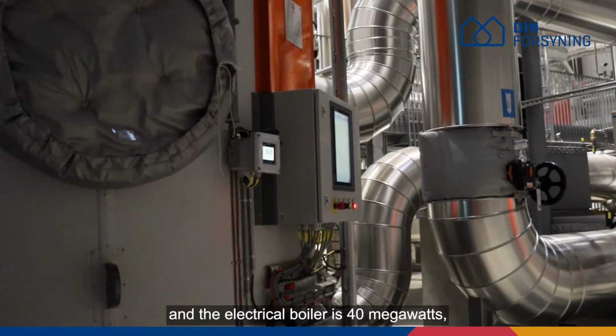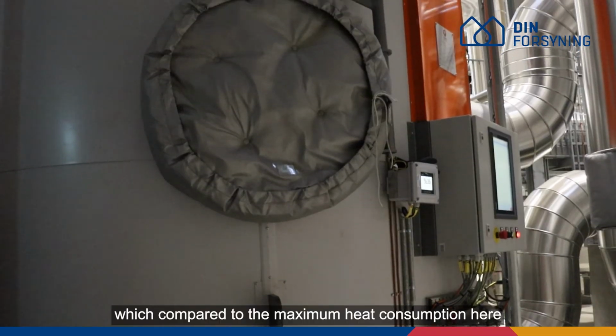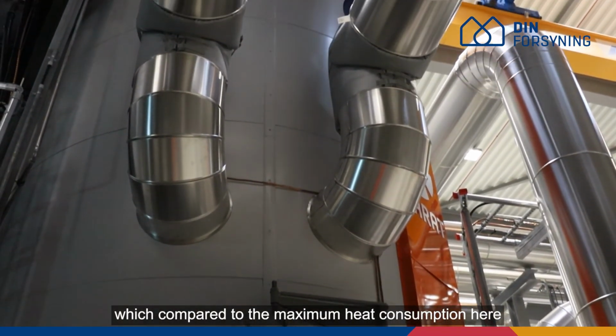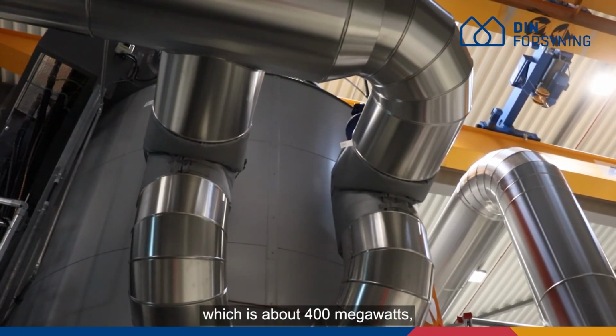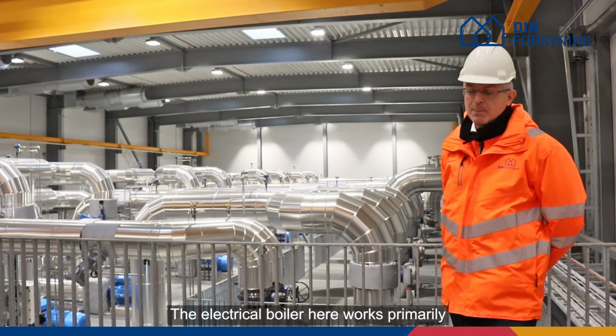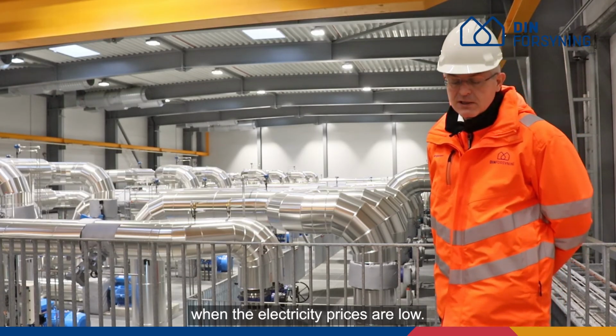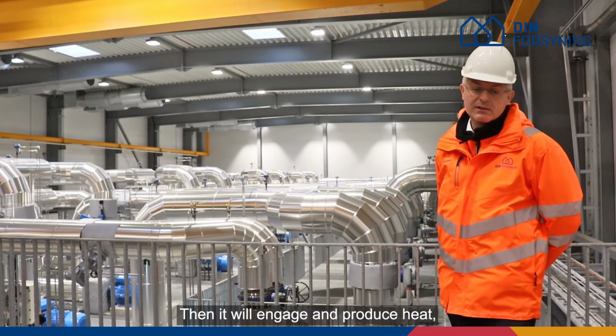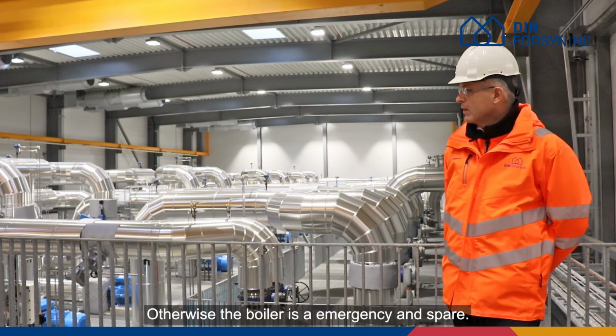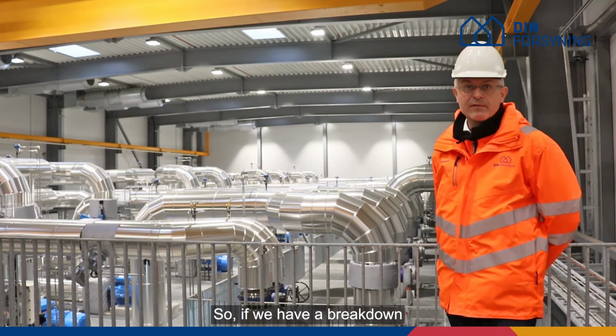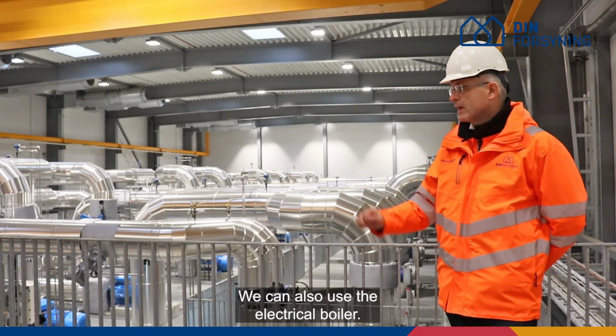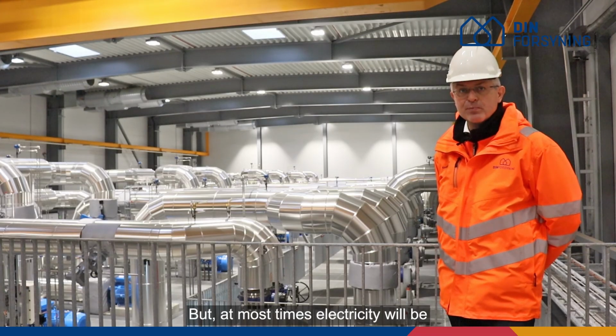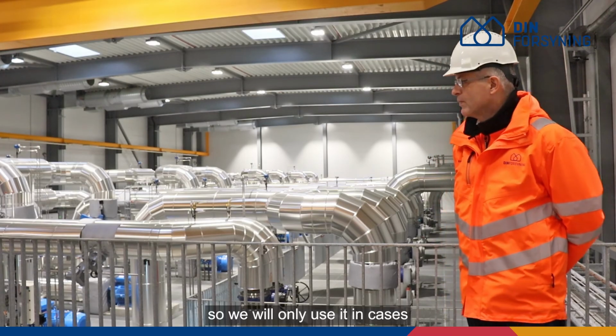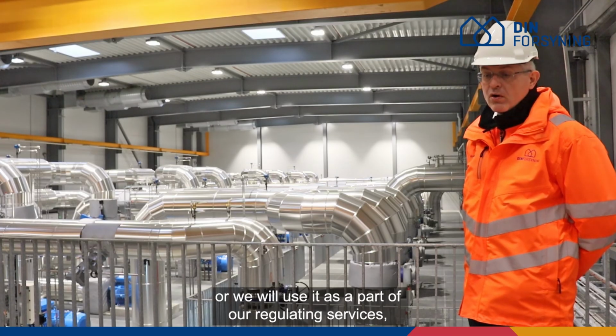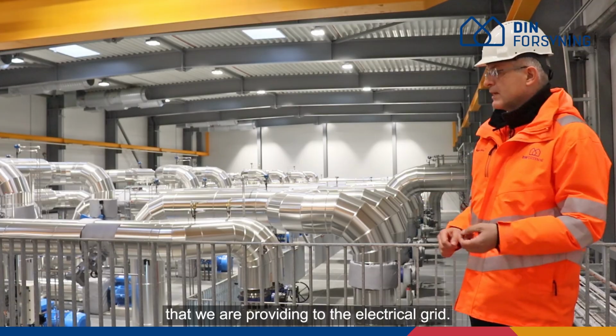In the same building, we have located our electrical boiler. And the electrical boiler is 40 megawatts, which compared to the maximum heat consumption here, which is about 400 megawatts, is about 10%. The electrical boiler here works primarily when the electricity prices are low. Then it will engage and produce heat if the prices are sufficiently low. Otherwise, the boiler is an emergency and spare. So if we have a breakdown of equipment in our system, we can also use the electrical boiler, but at most times electricity will be a very expensive heat source, so we will only use it in cases where it's very cheap, or we will use it as a part of our regulating services that we are providing to the electrical grid.